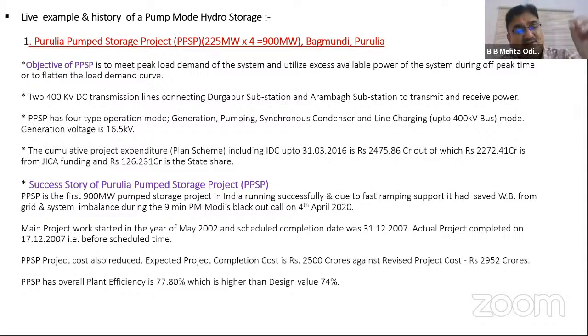It's not only that you meet your peak requirements, or pump during off-peak periods - even if your power may not be surplus to pump it, if the market rate is competitive, pump it anyway and use it as a motor to store that energy. When the exchange rate is 2 rupees or less, you can sell it at 6 to 8 rupees during peak hours. With that difference between peak and off-peak or lean period rates, even with 70-80% efficiency, pump mode is viable, doable, and leads to very good balancing for the grid operator.